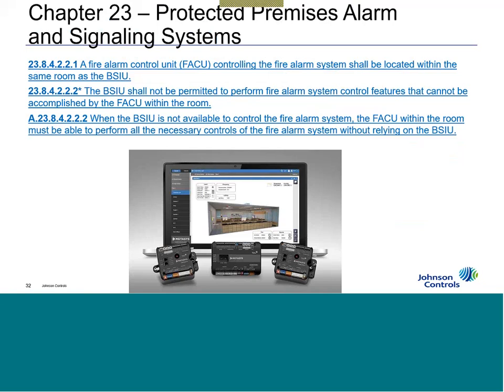So it just can't be an annunciator there, because I can't do disabling, enabling of points, controlling things. But if all I'm limiting my software to on my BSIU is just silence and reset and that's it, well, then an annunciator could suffice because it's mimicking what I was able to do with the BSIU. You're able to turn a lot of these features on and off as they're installed. And the BSIU shall not be permitted to perform fire alarm control features that cannot be done by the FACU in the room. So that's a key point.